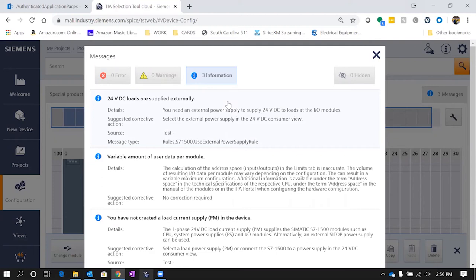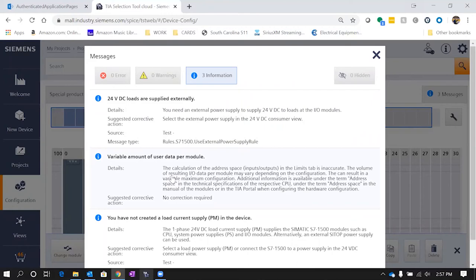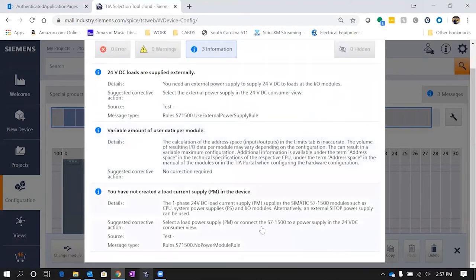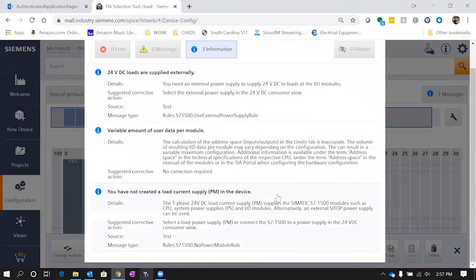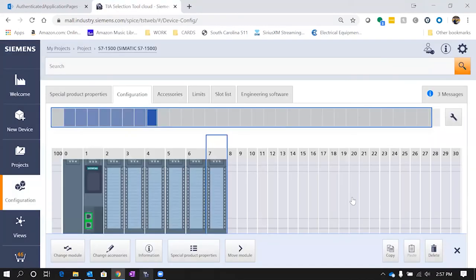So now you can tell here for our external loads we need an external power supply, and also it does the calculations and things in there to kind of tell you what size memory card you might need. Here's another note in here telling you about your 24 volt DC load. We entered a 24 volt power supply, but this is telling you that you can use a load power supply to supply load to your input/output modules just like right here in that message.